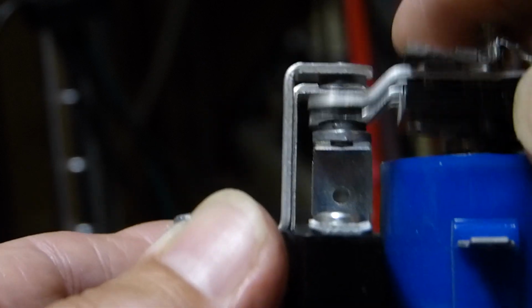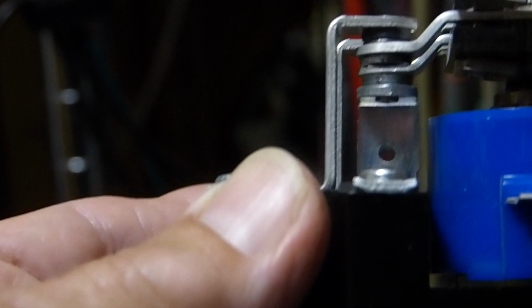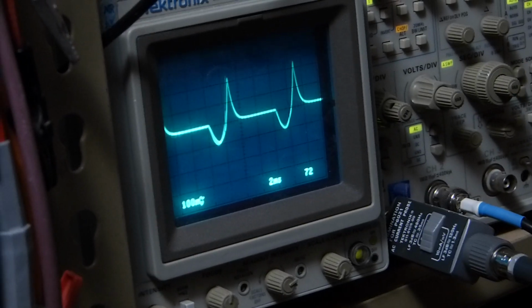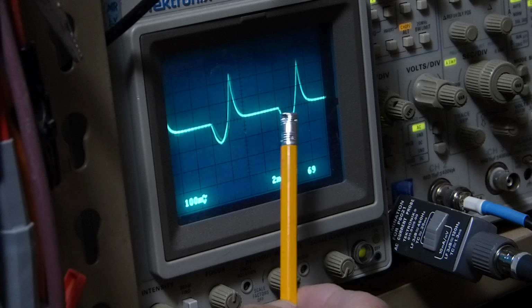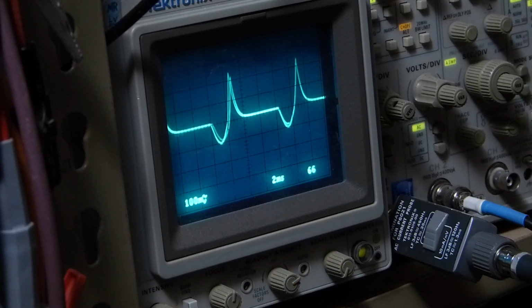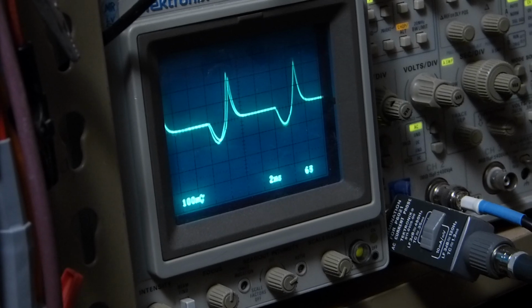But that's the problem — if this thing continues to arc, well, in 10 minutes it's going to be burnt up, or less. So you've got a problem. You've got a completely different kind of problem when you put a contact switch or a relay in a DC circuit, because you're never turning the current off. The current's flowing all the time, and then all of a sudden you open the switch and the current doesn't want to quit flowing. So it makes that arc, and if the contacts don't come far enough apart, it never quits arcing. Well, when we're looking at this right here, it's going to quit arcing because the current goes to absolute zero right there.